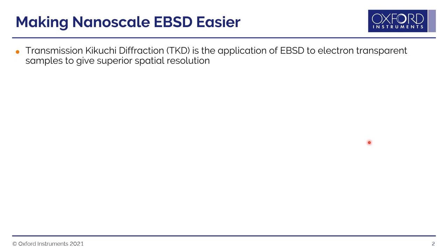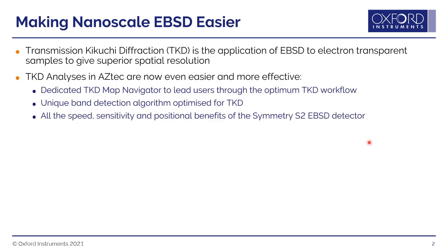The first thing I want to talk about is how we're making nanoscale EBSD easier, and this is done using Transmission Kikuchi Diffraction, which is essentially EBSD applied to electron transparent samples, giving us much better spatial resolution. In Aztec, we've introduced a dedicated TKD map navigator that leads the user step-by-step through this slightly modified process of collecting good quality TKD data. This also incorporates our unique band detection algorithm that has been specially optimized for the unique geometry of TKD, so we get really good quality data all the time.